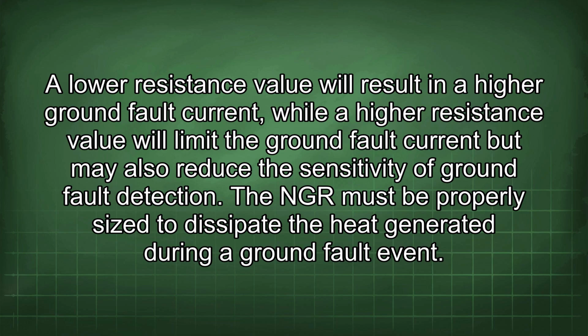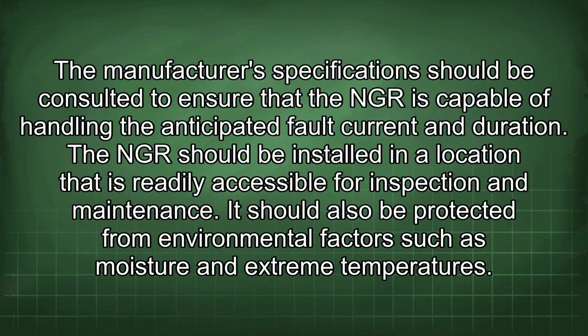The NGR must be properly sized to dissipate the heat generated during a ground fault event. The manufacturer's specifications should be consulted to ensure that the NGR is capable of handling the anticipated fault current and duration. The NGR should be installed in a location that is readily accessible for inspection and maintenance. It should also be protected from environmental factors such as moisture and extreme temperatures.